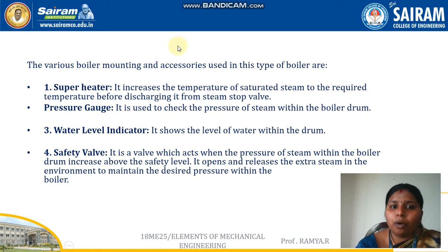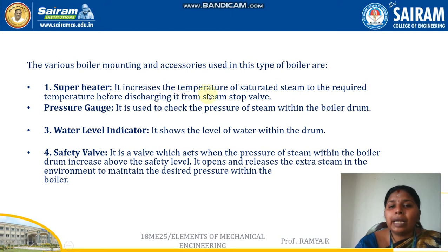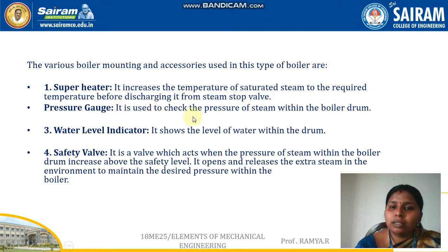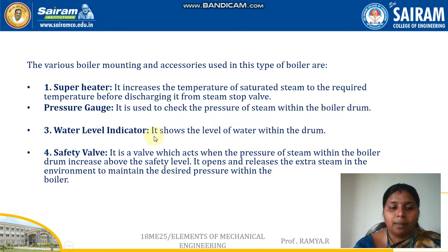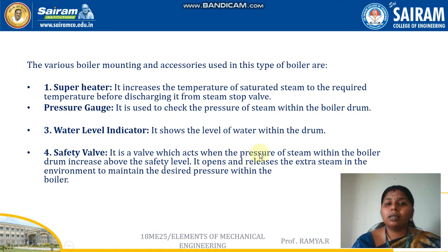Regarding boiler mountings and accessories: the superheater increases the temperature of steam to the required level before discharging it through the steam stop valve. The pressure gauge checks the pressure of steam within the boiler drum to avoid accidents. The water level indicator shows the level of water within the drum. The safety valve releases excess pressure when it becomes too high, to prevent accidents.